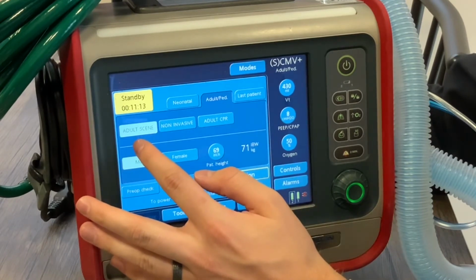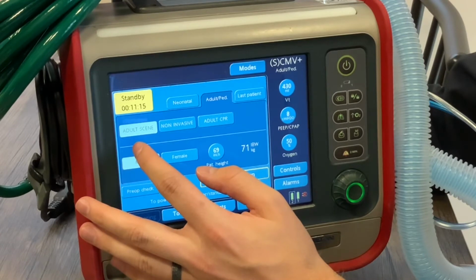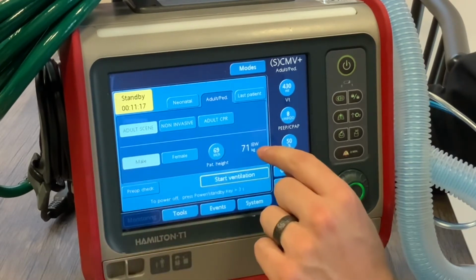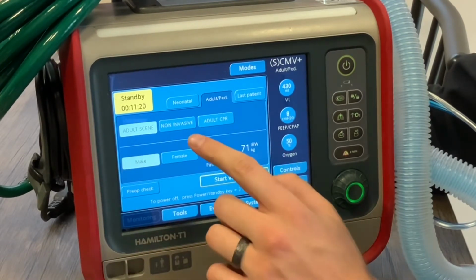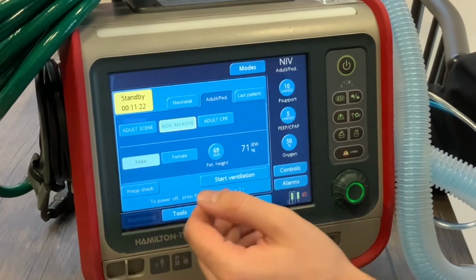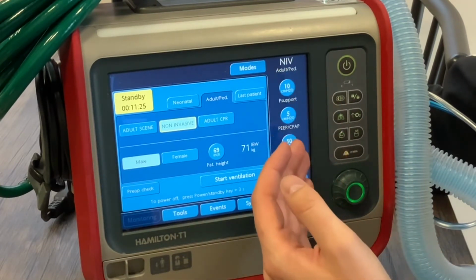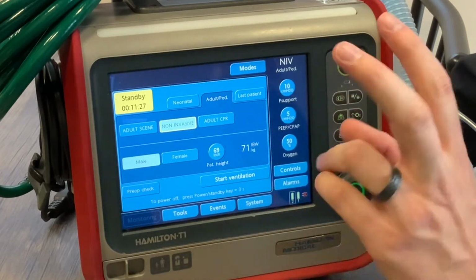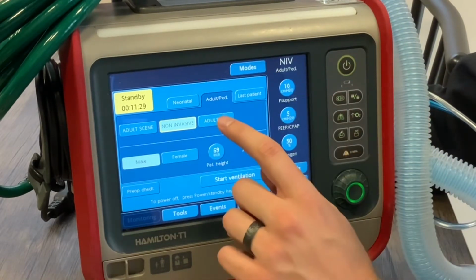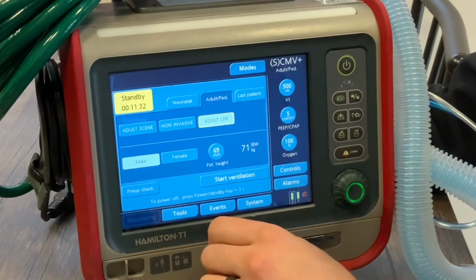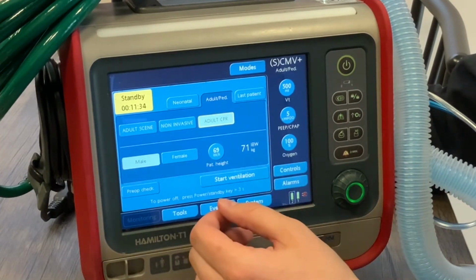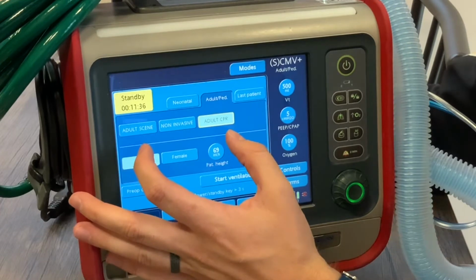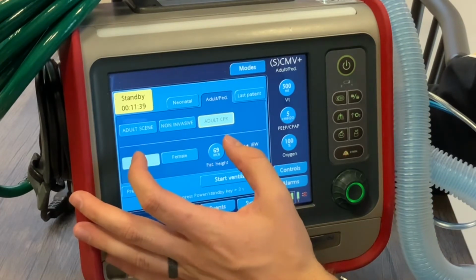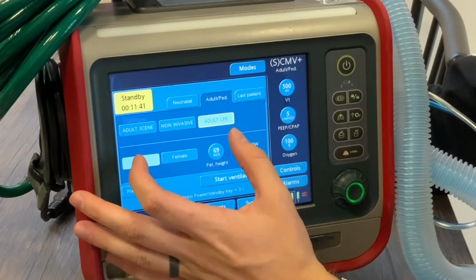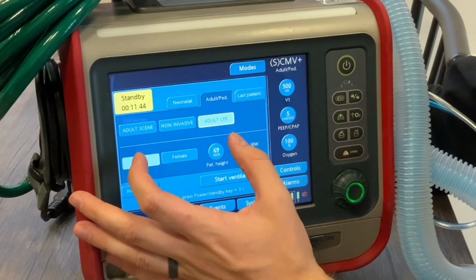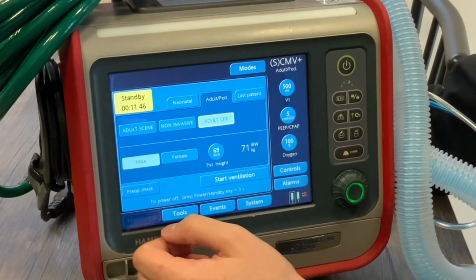Adult scene is set up with CMV plus for 6 cc's per kilo of a 71 kilogram patient. We have a non-invasive feature, which is 10/5. As a reminder for BiPAP, this is additive. 15/5 would be the total. And an adult CPR mode, which we'll go into a little bit later. These 3 modes are meant to get you started when quite busy. We should not rely on these, as the cookie cutter modes will not be one size fits all, but this is a place to get you started.